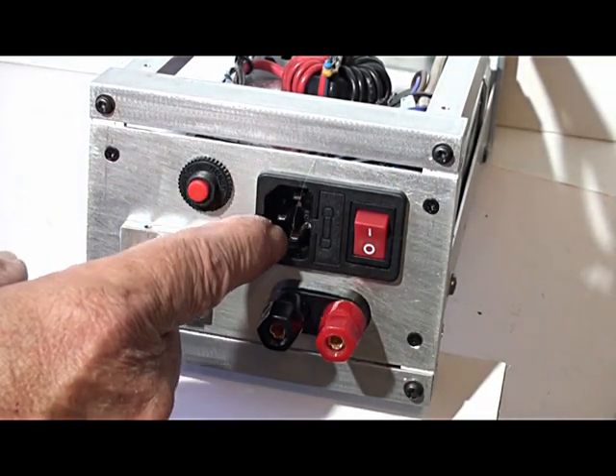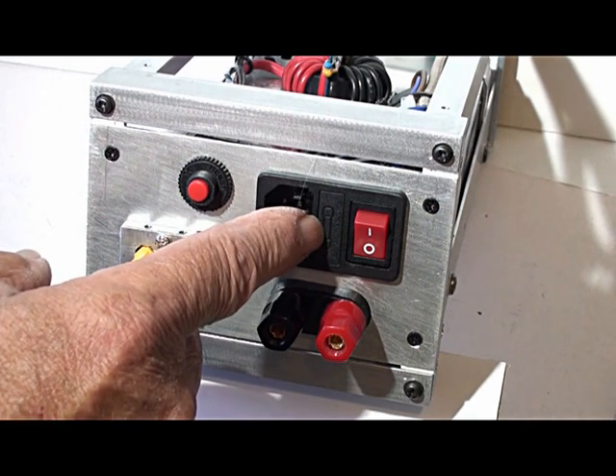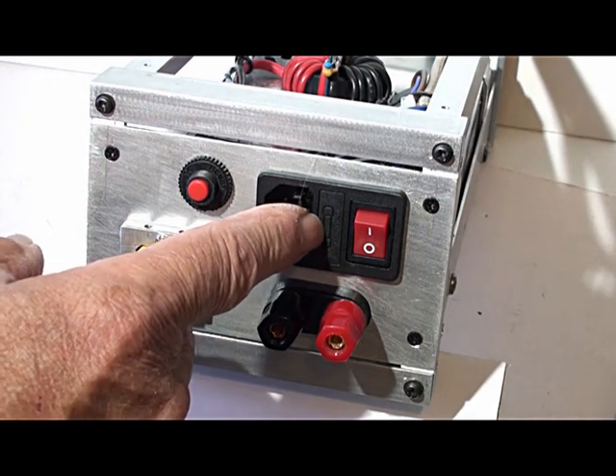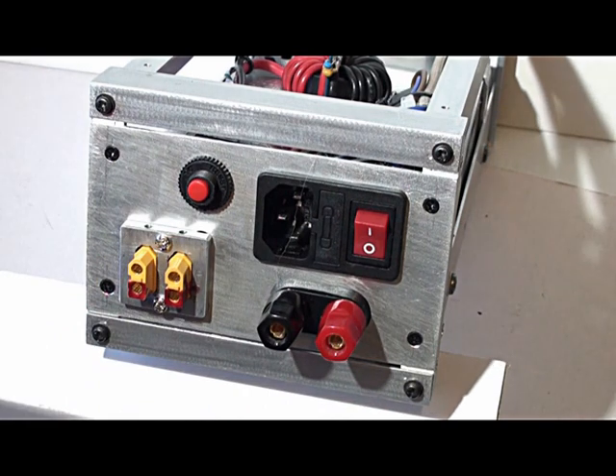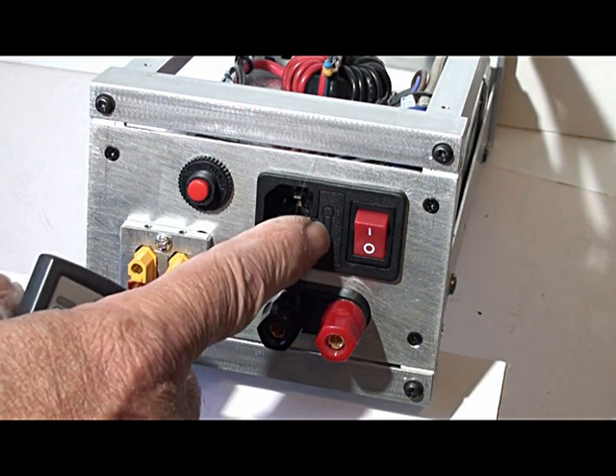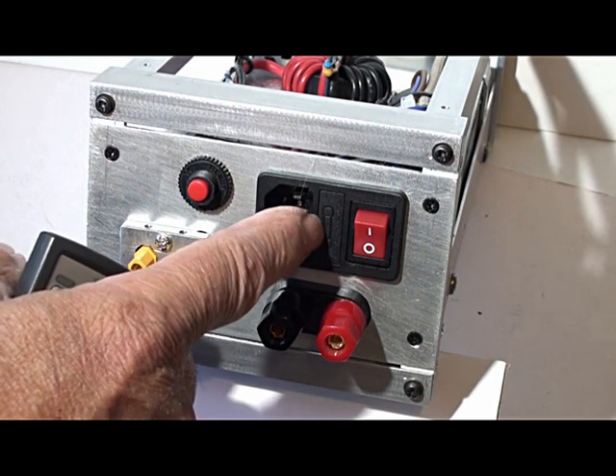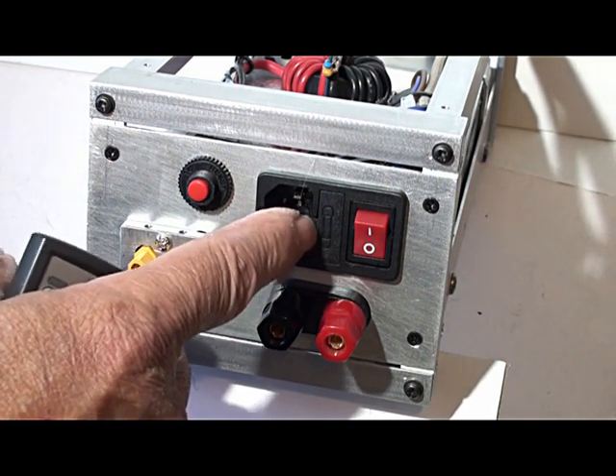The input is an IEC connector on a panel which also has an inbuilt fuse and an on-off switch. The actual power supply has an internal fuse that's normally soldered in, a 6.3 amp slow-blow type. However, I've removed that and replaced it with an M205 fuse holder with an 8 amp time delay fuse, and I've put the original 6.3 amp fuse inside this container so it's easy to get to if something blows up.